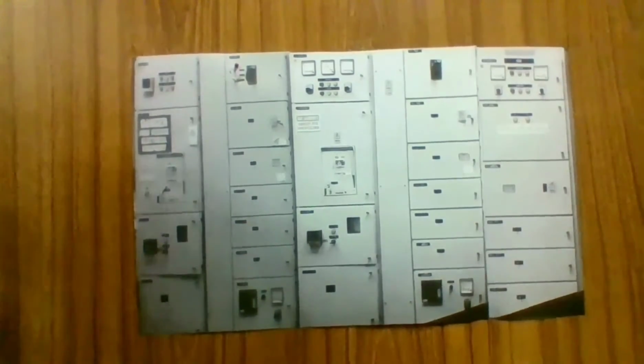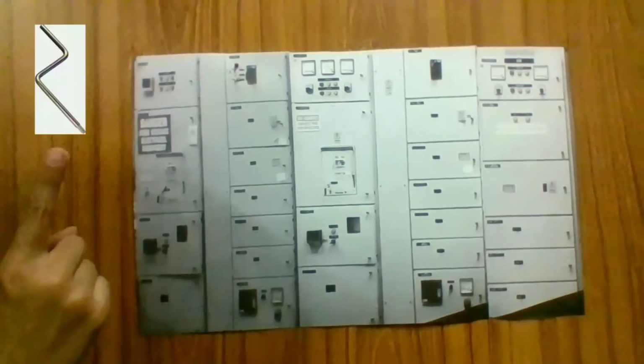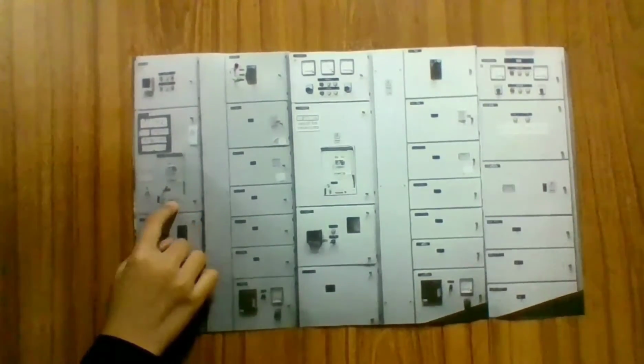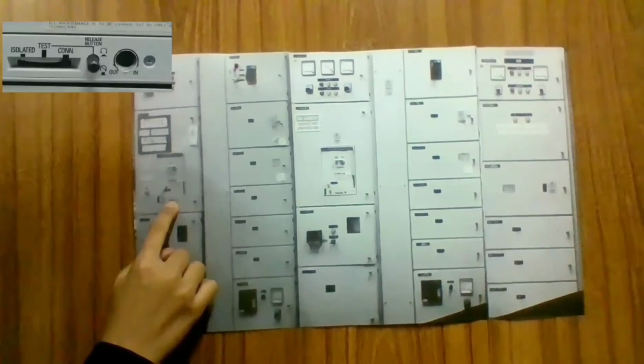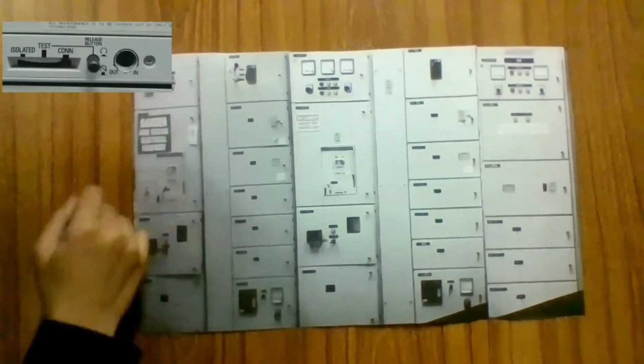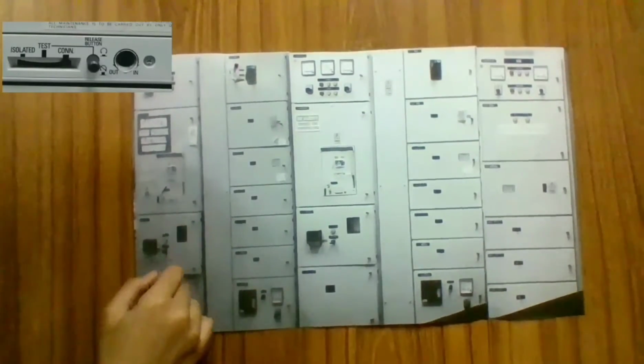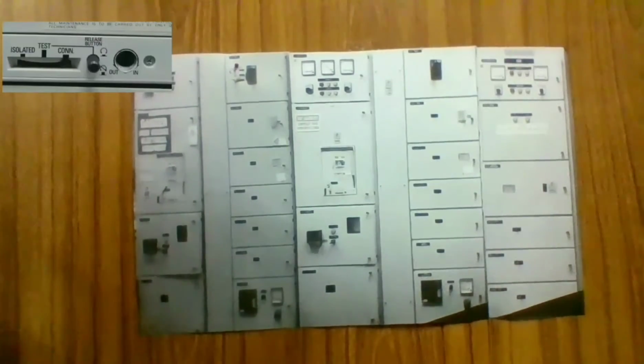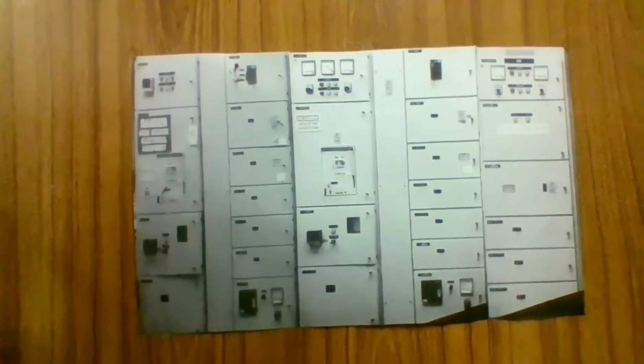Next, to remove the ACB, hold the release button and put the racking handle into the insertion hole. Rotate the racking handle anti-clockwise until it stays at isolated condition. Now the ACB is disconnected from the busbar.